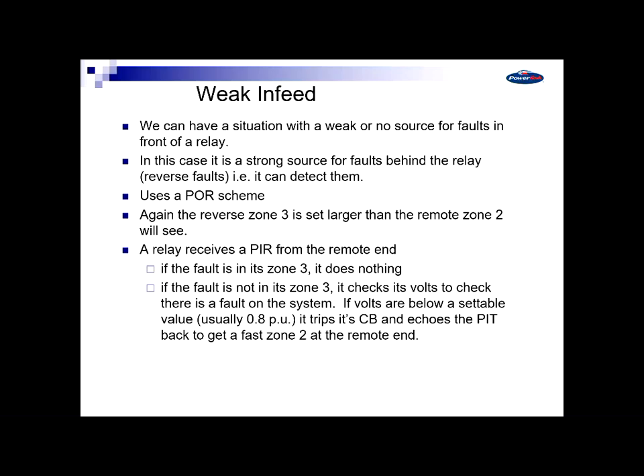I've told you you're weak in feed, that you're blind to faults in front of you. I can see a fault in front of me. Then we just make the logical conclusion that the fault must be on the feeder. So you echo that signal back to me. So if it was in my zone 2, I'll go quickly. If it was in my zone 1, I've already tripped. So you trip and echo a signal back to me.